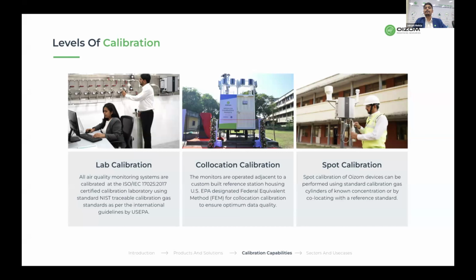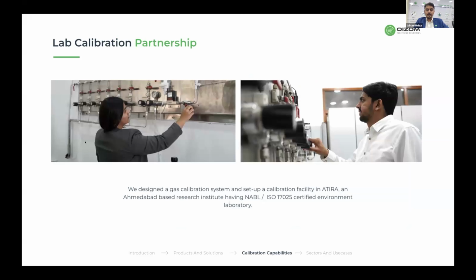However, in critical applications, should you require to do a span calibration, that can also be done on site. Oizom offers a calibration training as well as a calibration kit for you to conduct the calibration on site. What you saw on Envisom right now was the version that the users will be able to see. But your own version as an admin, you will also have the option of calibration module as well, which can be activated when you're calibrating a specific unit. Now, our lab calibration is in partnership with Atira.